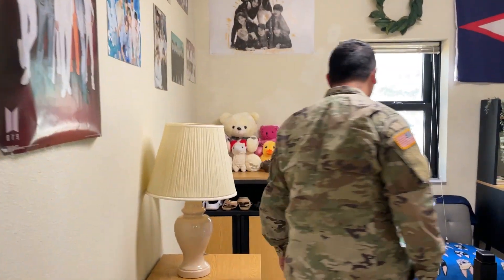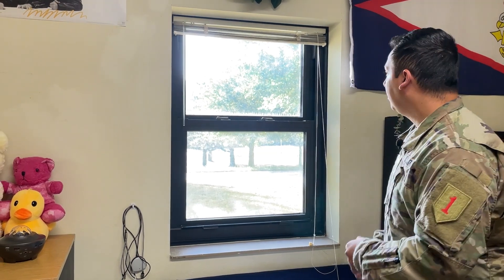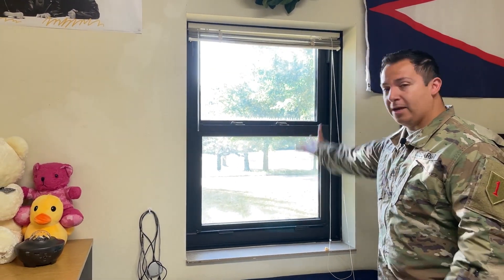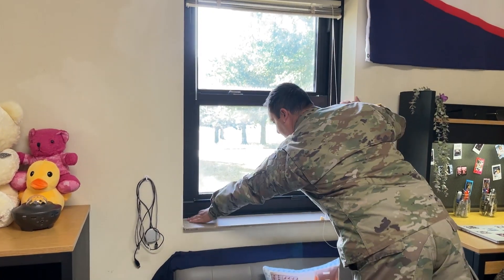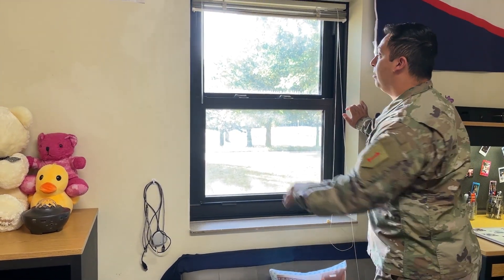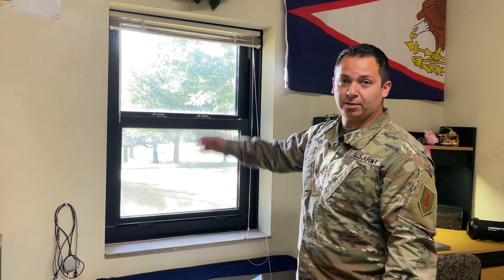One of the most important things in these rooms is the window itself. When looking at your soldier's window, make sure it's actually closed and closes and locks properly, especially in the summer. If you keep the window open, moisture will get drawn into the building and trigger the HVAC system to overwork itself and go down. To check the window, open it, make sure it opens properly, then close it and check for seals and any caulking. You'll see a line of caulking on the bottom and other caulking and different types of seals on the window — make sure that's clean. Also check your blinds to make sure they're clear of any debris, dust, or moisture.